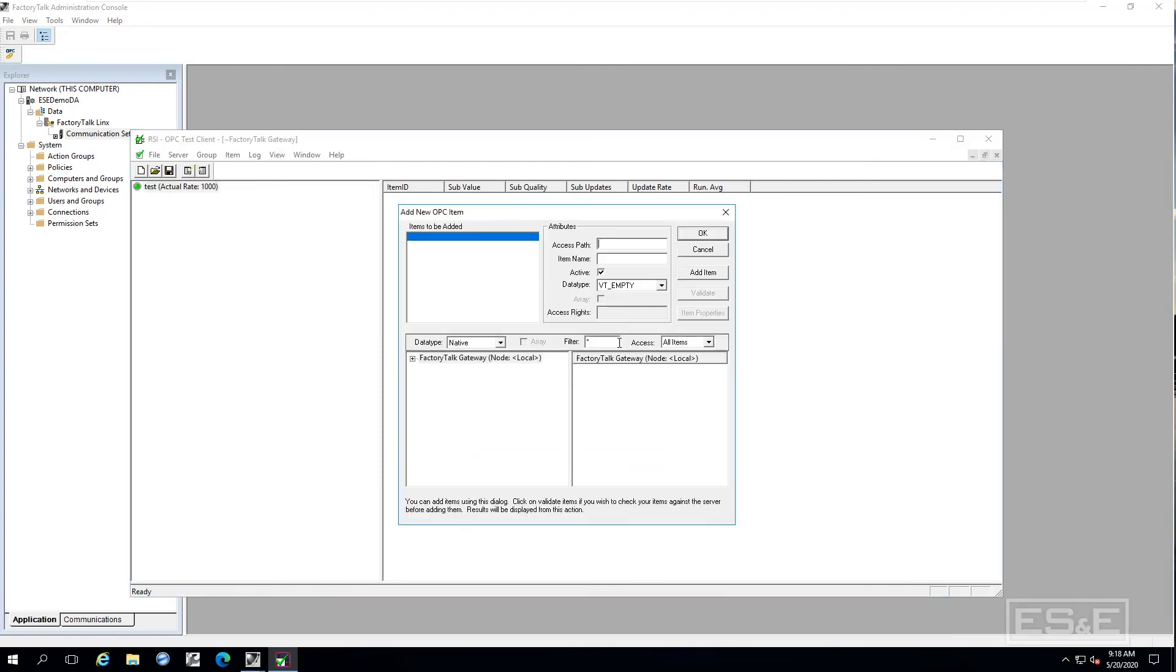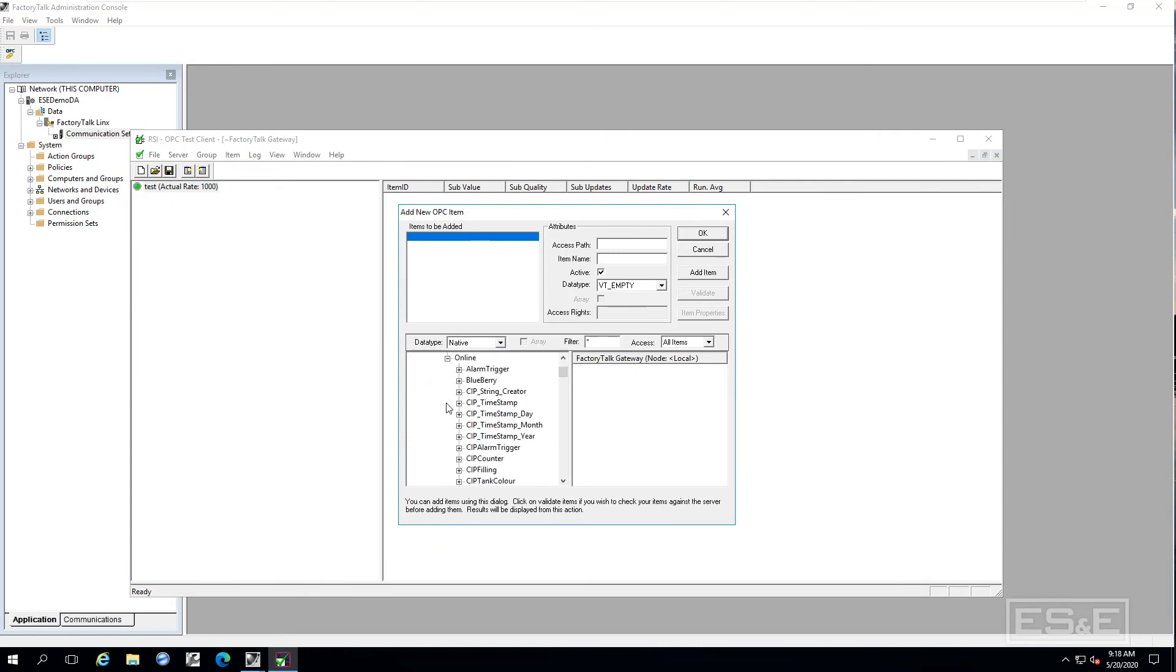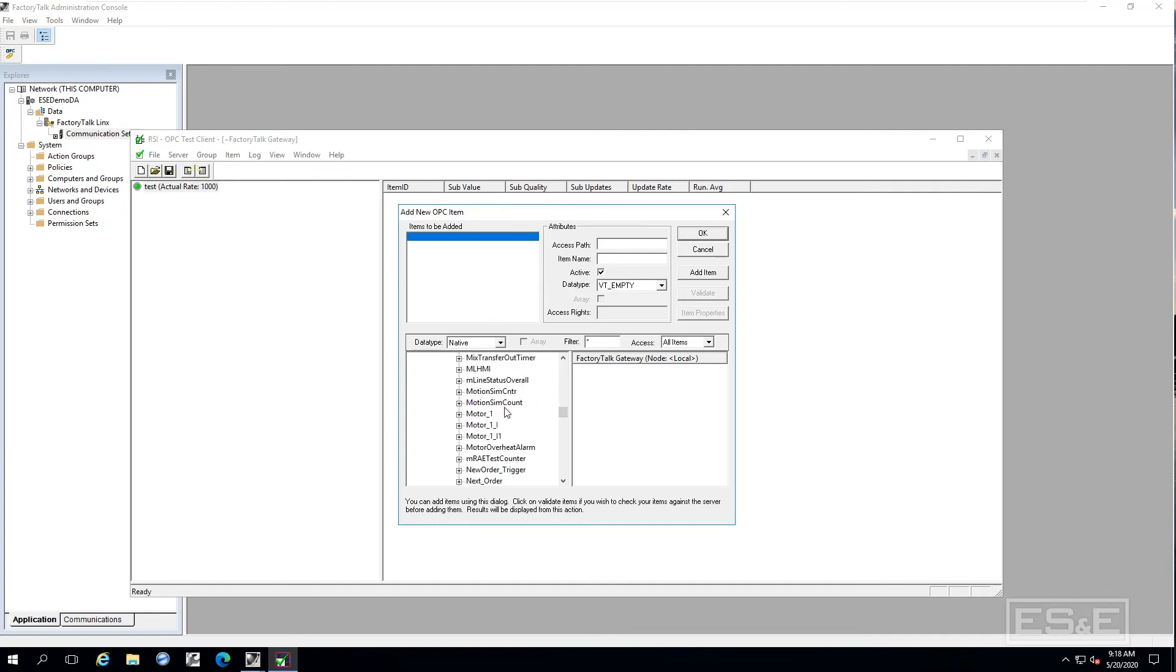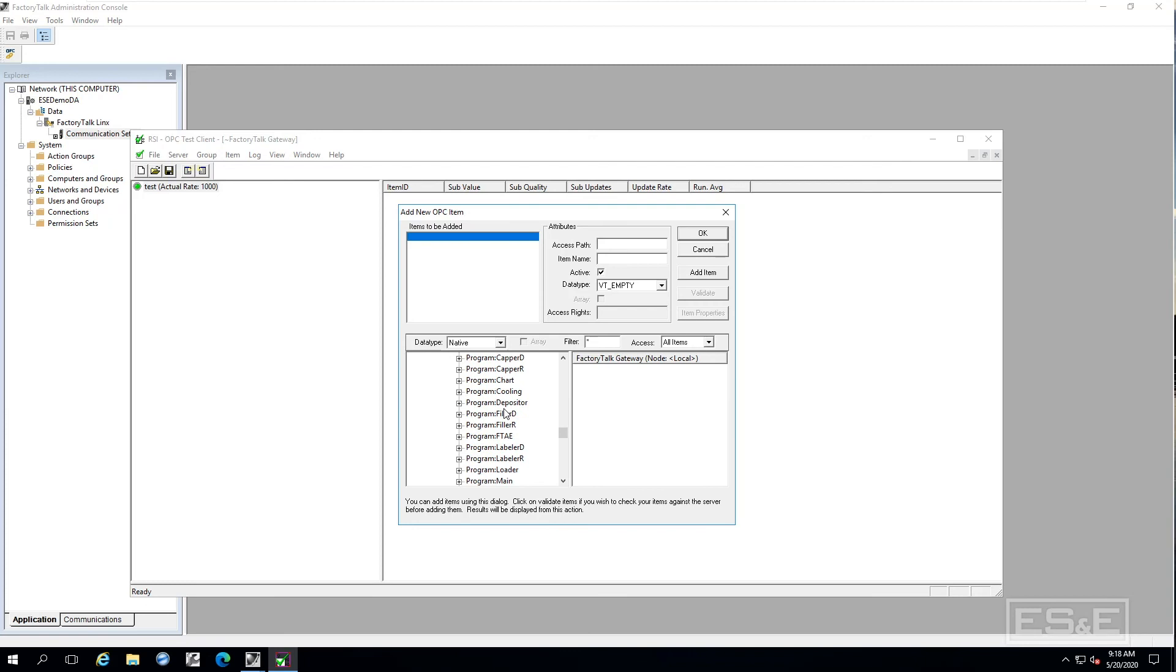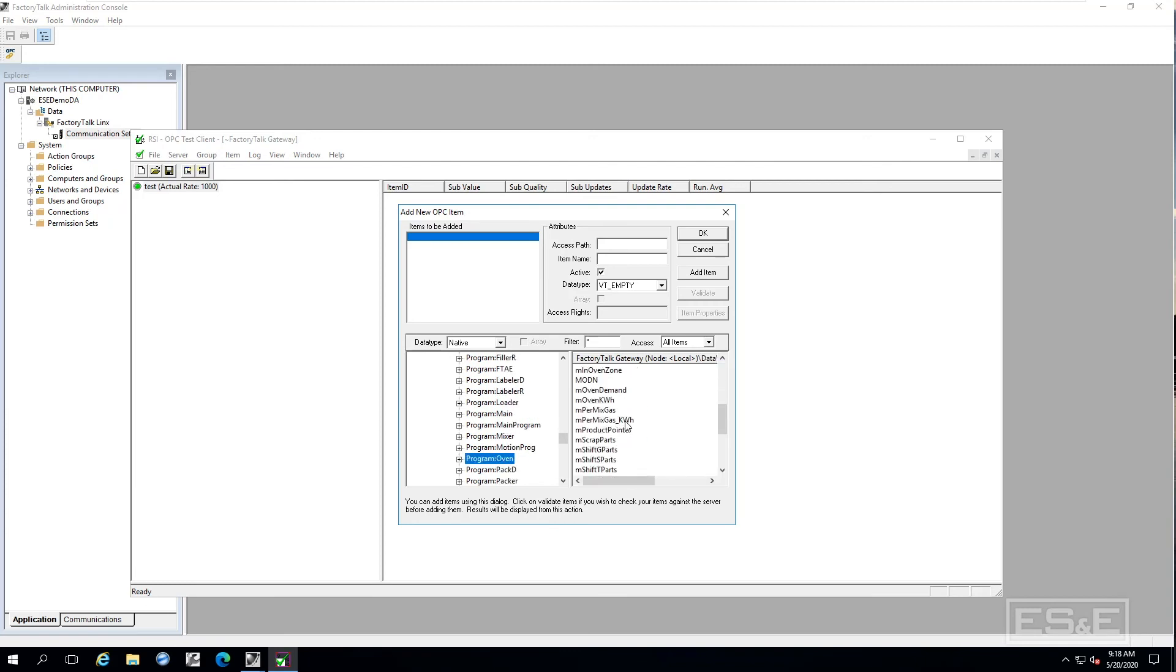Now I am just going to add an item and you can see I got the factory talk gateway. It has my server. I am just browsing down to the controller and let us select the same one we did before, the same tag. Look at that oven temperature and verify that we are actually getting data. Say okay.